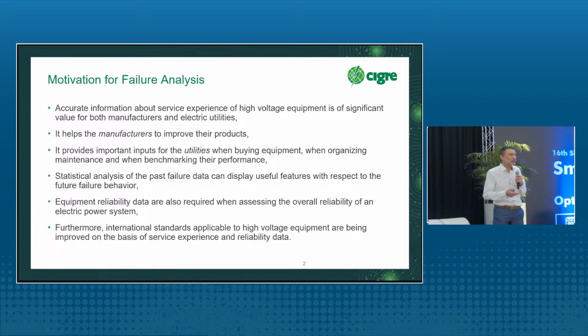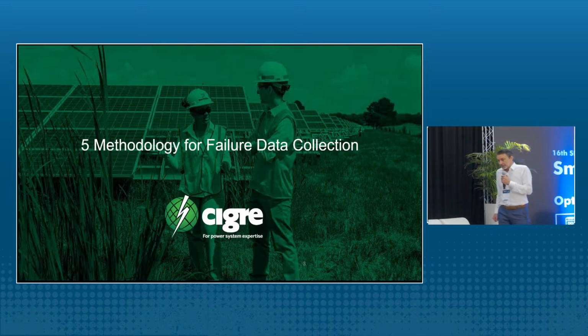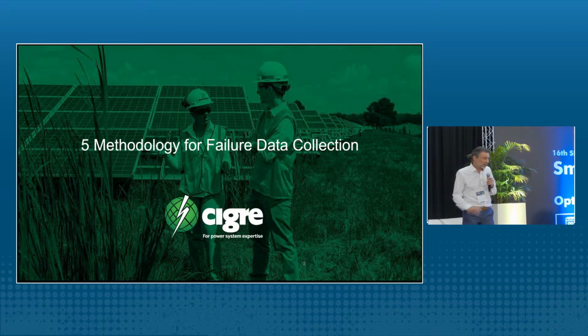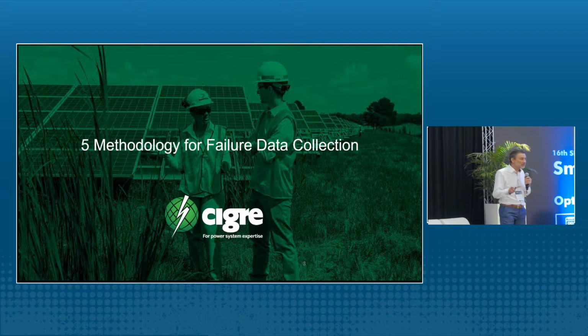So it is quite important to know how often failures and why failures occur within power transformers. In the brochure we have a large chapter written on, for example, what measures you can take in a transformer to increase the reliability. Simply this would have been too much for the 25 minutes where I will talk on transformer reliability. So I will just explain here why and when transformers fail. And in order to know this, of course, you have to ask the utilities, when and why do your transformers fail?